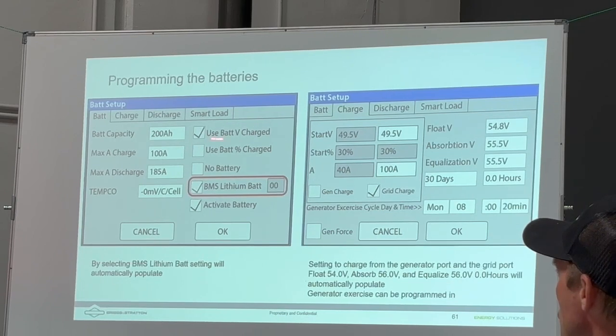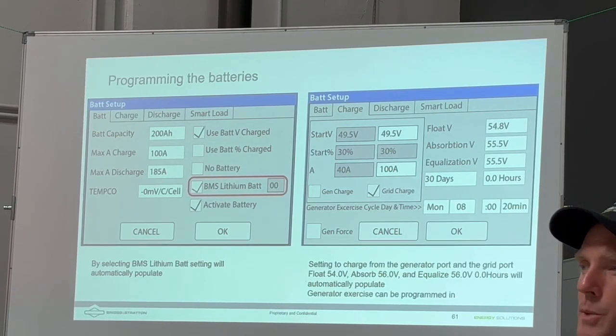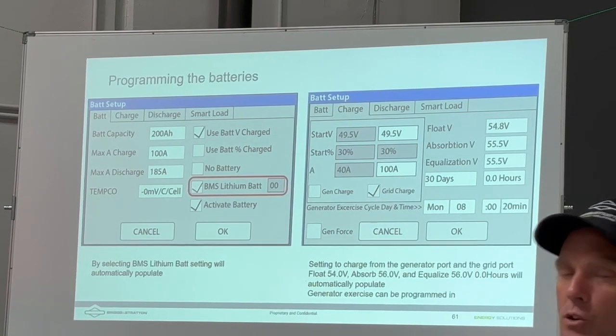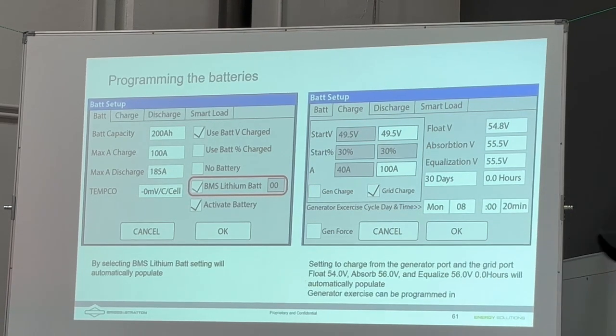If I have used battery voltage here, it would display my settings in voltages. It used to be we would program them based on voltages. If you use percentage, it will show you everything in percent. So for instance, grid charge is enabled right here. The voltage box was checked here, and so you can see that the voltage is what's displayed here and the percentage is grayed out. If I had selected the percentage here, then the voltage would be grayed out and the percentage would be displayed. And all of these are grayed out here because we don't have the gen box checked.